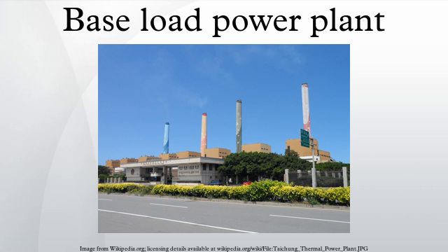Baseload generators, such as nuclear and coal, often have very high fixed costs, high plant load factor and very low marginal costs. On the other hand, peak load generators, such as natural gas, have low fixed costs, low plant load factor and high marginal costs. Typically baseload plants are large and provide a majority of the power used by a grid. Thus, they are more effective when used continuously to cover the power baseload required by the grid.